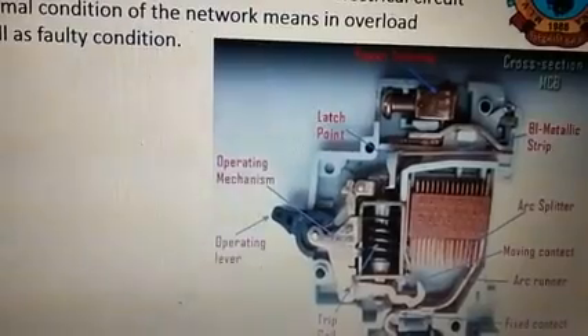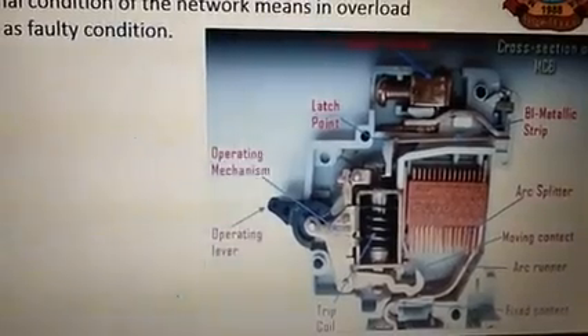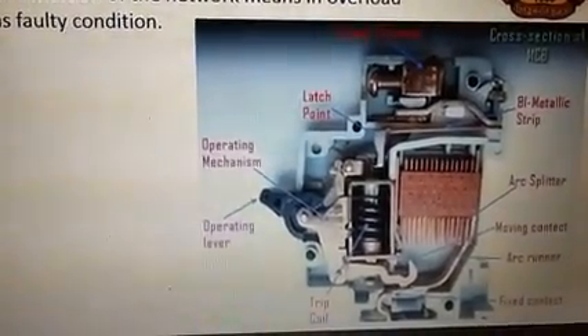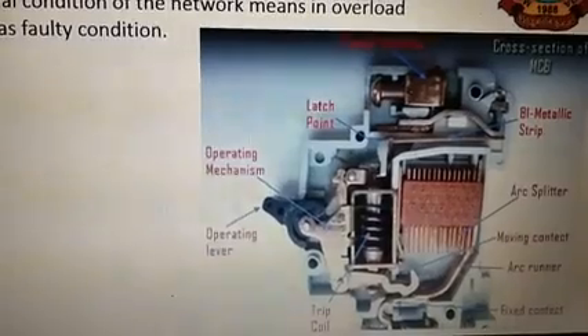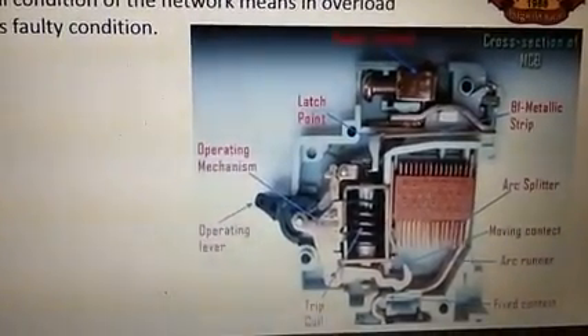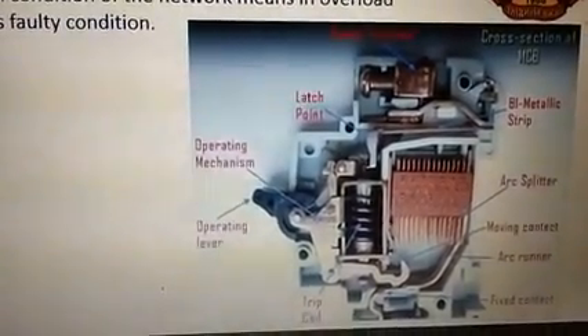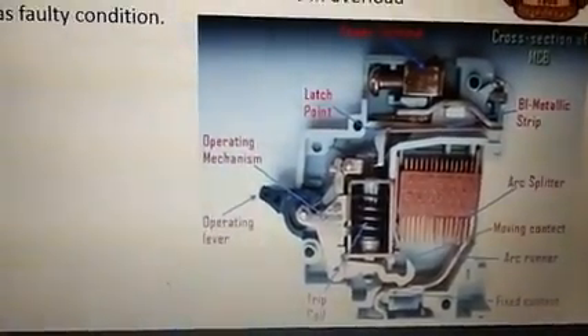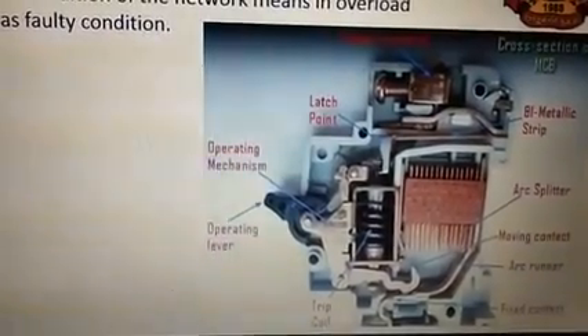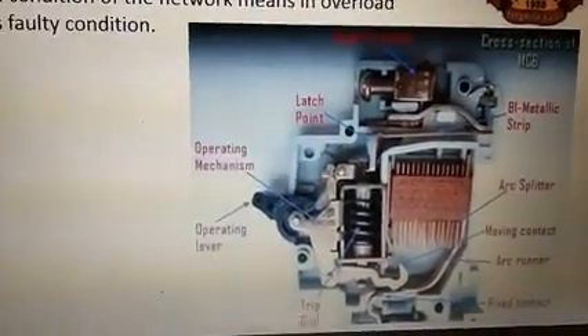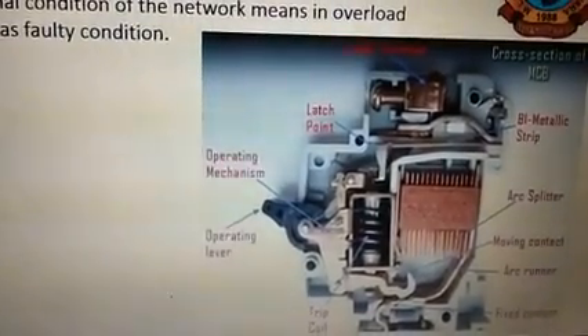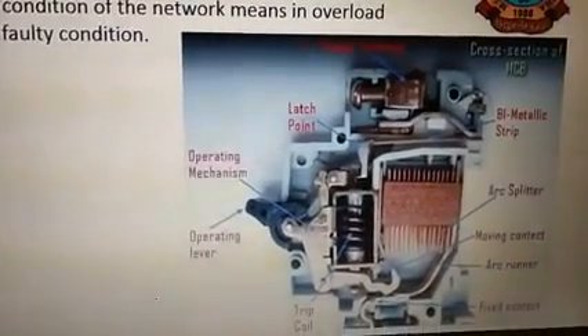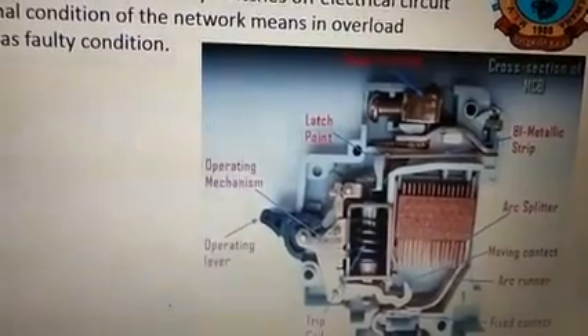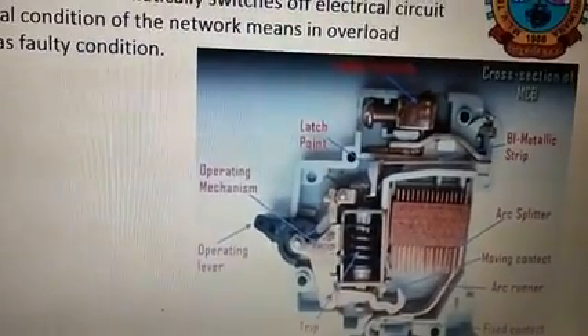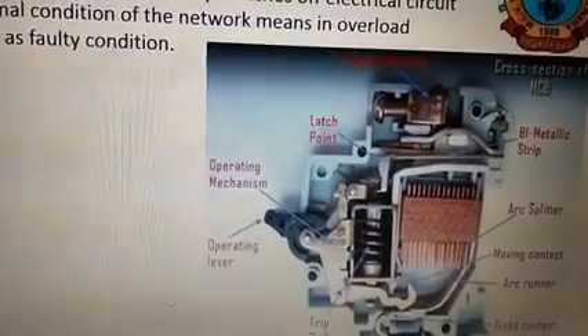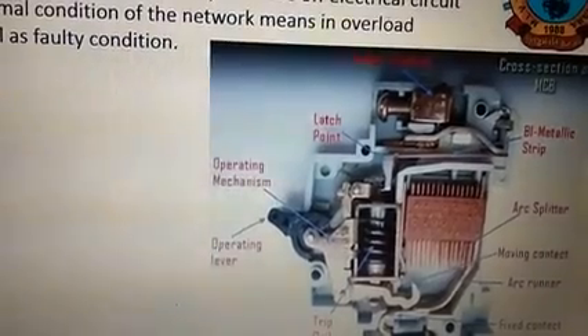So if we see the conclusion of the working of this MCB, you have 3 points: the bimetallic strip, the magnet and the operating lever. It can be turned off in 3 cases. So this is the beauty of the MCB. It provides 3 mechanisms in a single miniature circuit breaker to make it switch off. We will find there are mainly one bimetallic strip, one trip coil and one hand operated on off lever. This is the electric current carrying path of a miniature circuit breaker.